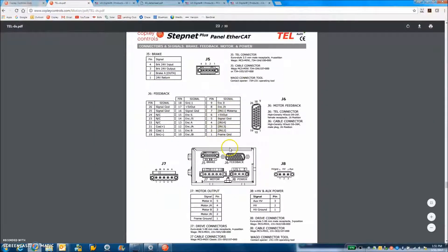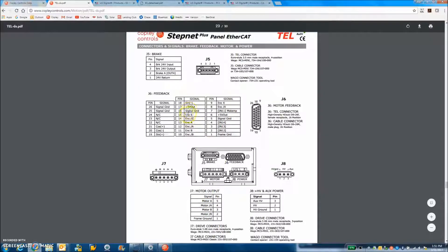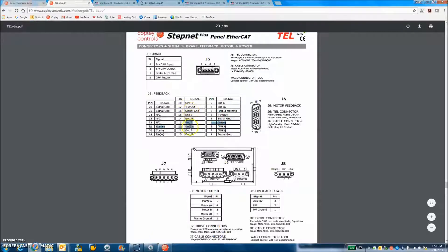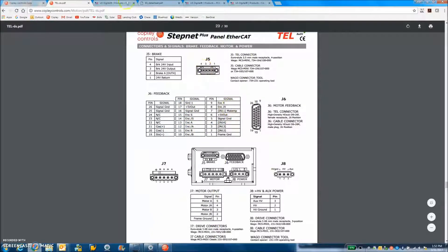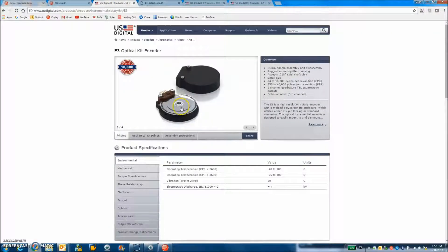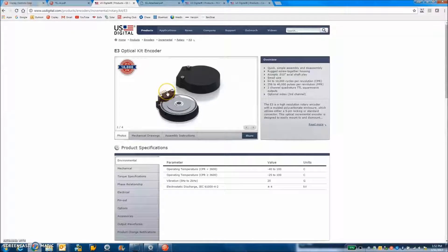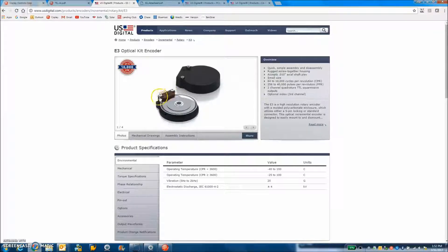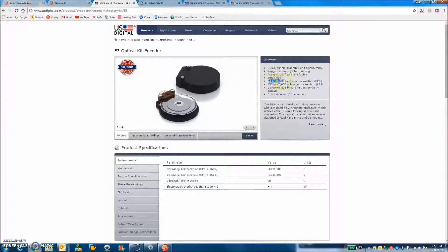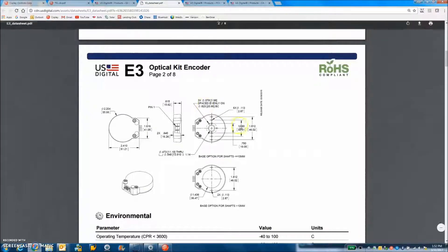On the TEL, of course, we connected the motor motor power wires. But this device has an incremental encoder. So we hooked up plus five and ground, A, A naught, B, B naught, and X, X naught, which is index. The encoder mounted to the back of the stepping motor. This is a single-ended HP type of device that reads the lines. This has a 1,000 line or 4,000 counts, but there's options to go up to 10,000 counts per rev.